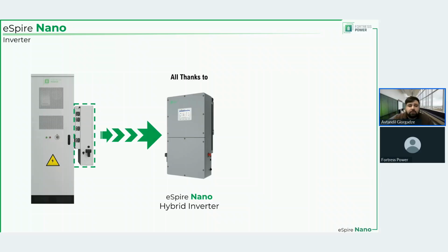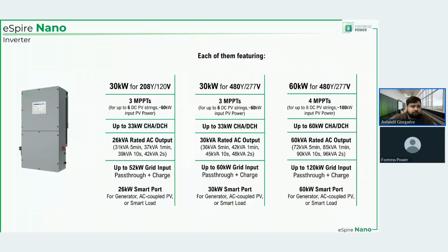So, quick recap on the inverter performance summary. We have 2 30 kilowatt units available, one for 208 and one for 480 volt systems. We also have 60 kilowatt inverter for 480 systems. The name of the inverter really suggests the rated output of the inverter on the AC side, except for the 30 kilowatt for 208, which has 26 kilowatt or kVA rated AC output. But in terms of features, they're all the same. Power ratings are different, and also 60 kilowatt inverter compared to 30 kilowatt units has one more MPPT.